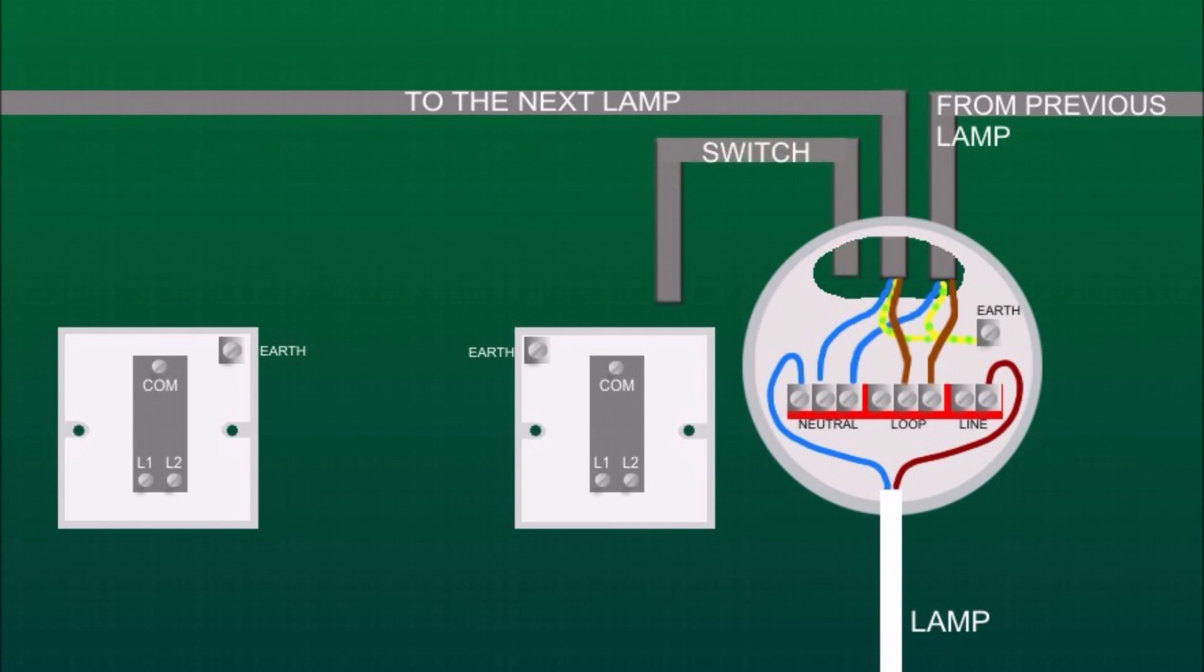Now the first switch is also wired to the ceiling rose with twin and earth cable. At the ceiling rose, earth wire to the earth terminal, live wire to the loop, and blue wire to neutral terminal.